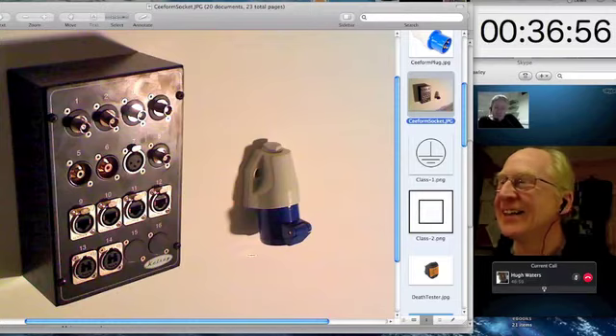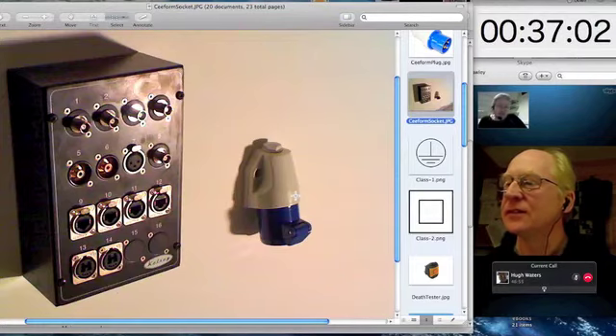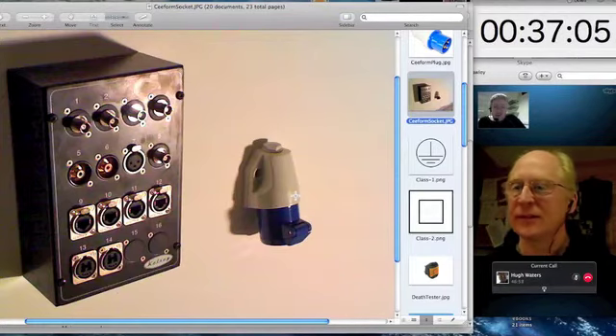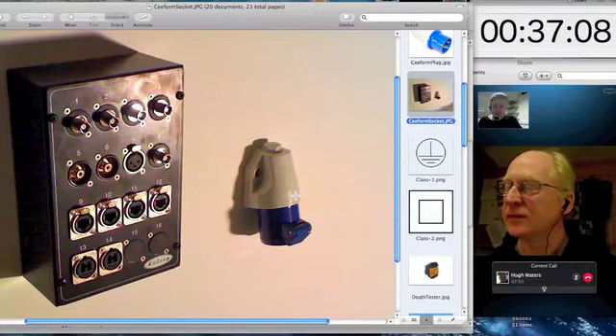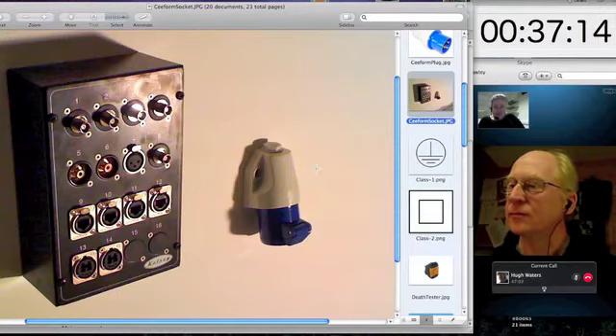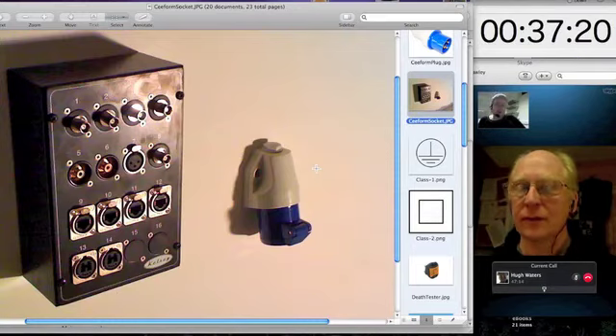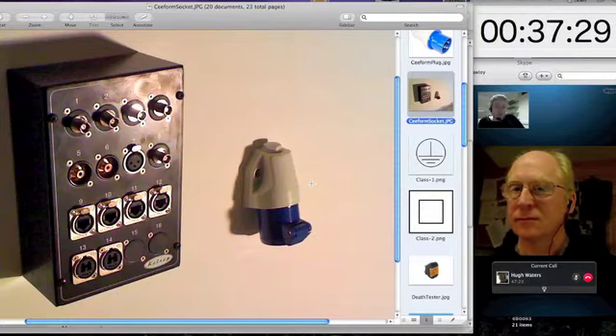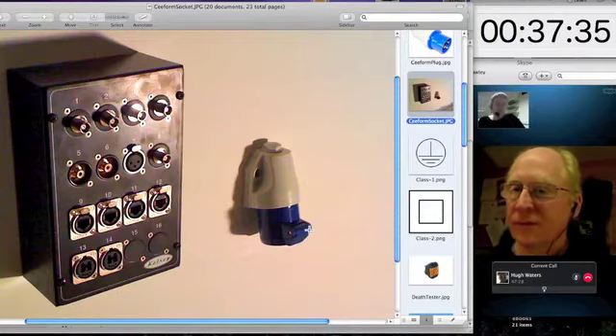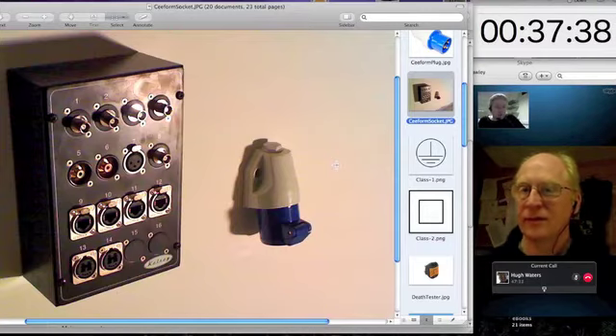But mounted next to the wall box on the wall is a 16 amp C-form commando connector, as electricians like to call it, and that's the technical mains for that room. So what we would do is, when the edit desk gets brought into that room, the power distribution unit within the edit desk will be fed off that 16 amp C-form, and anything that's in the production chain, monitors, the Avid maybe, the Final Cut workstation, whatever, would all be fed off that same supply. And I know, because I specified this to the electrician, that that 16 amp C-form connector goes back to the same breaker board as the supply that feeds the machine room. So I'm certain that the earth provided on that 16 amp C-form connector is the same earth that's provided to all the production equipment in the machine room.